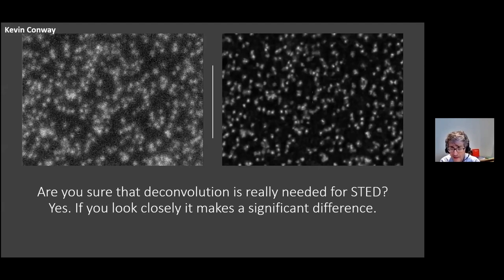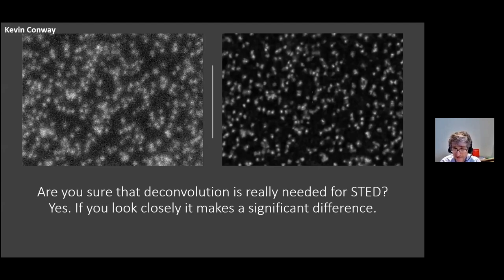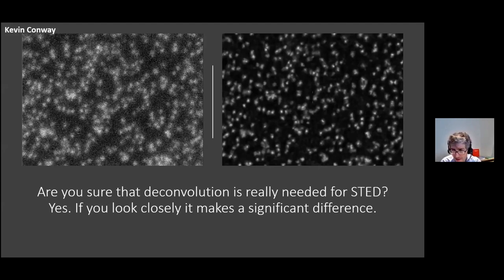With a quick and dirty full-width at half maximum measurement, I was able to get around 68 nanometers. That was literally 30 to 40 minutes of work on the STED. As Paul said, it's not the doing the STED that's the hard part — it's the sample prep. And the nice thing about commercial samples is you can walk people through training and give them an idea of what to expect without those sample prep questions.